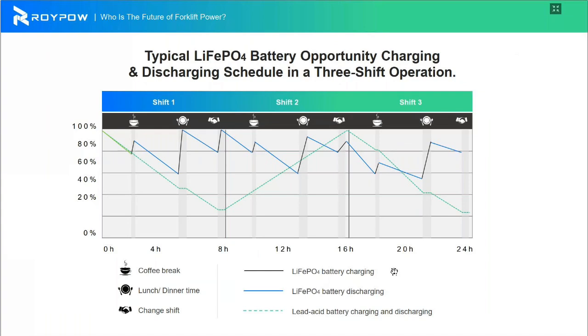This graph illustrates a typical opportunity charging and discharging schedule for a lithium LFP battery in 3-shift operation. The alternating black and blue lines represent the charge and discharge curve of the lithium battery, with black indicating charging and blue indicating discharging. The green line represents the charge and discharge behavior of the lead-acid battery. Let's take a look at the lithium battery usage first.